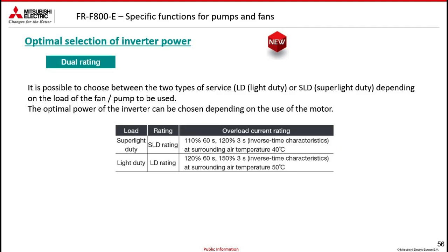A peculiarity of this inverter is the possibility of selecting the optimal power of the inverter. In fact, a rating is defined where, by means of a parameter, I can choose between two types of service, light duty or super light duty, based on the load that I will use. In fact, the table contains information relating to the overload. In super light duty, I will have a decrease of these values as the nominal current will rise.